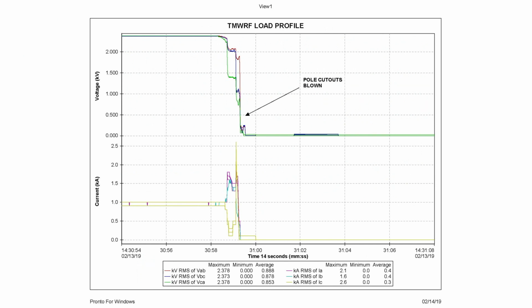So here's where the cutouts blew because we lost power. Voltage went from 2.4 kV down to 0. The amps, when that happened, went to almost 3,000 amps at that instant. And this is 14 seconds from here to here. So that arc flash happened right in that time frame. And A phase and C phase generated 2.1 and 2.6 thousand amps.